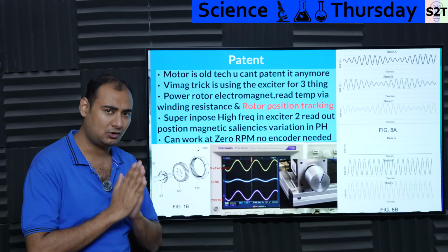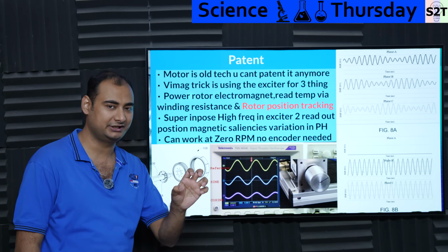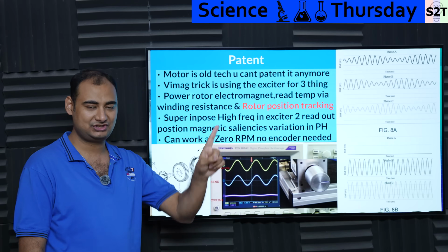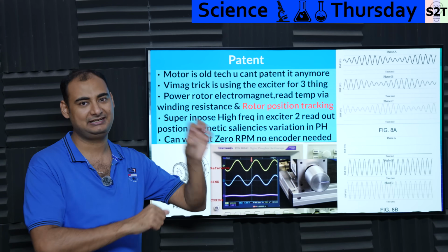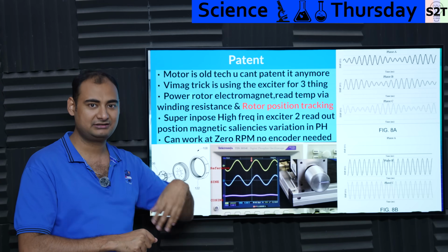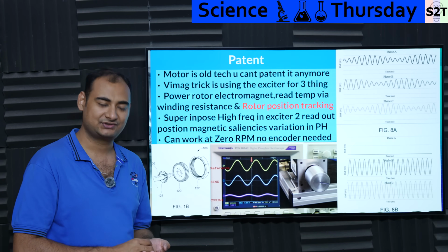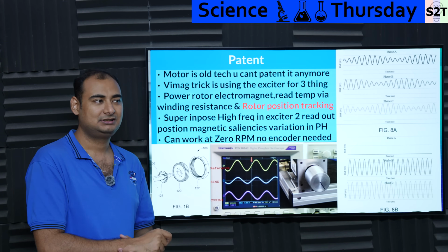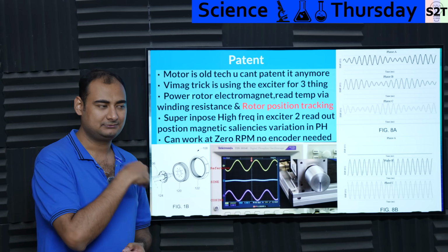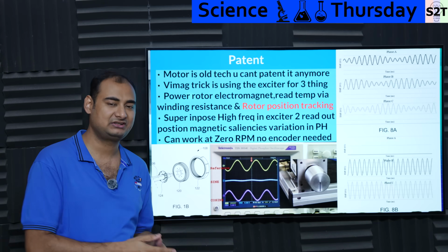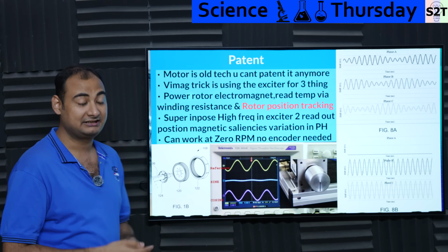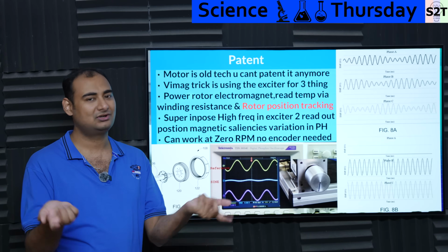Right now, if you look at all electric cars, they have an actual encoder that tells the rotor position. So the switching - phase A, phase C, phase B - never backfires, because it has the absolute data from the rotor coming from the encoder. But an encoder is extra hassle, extra stuff. What if you don't want to have it? You must have seen cheap drones - they do not have encoders.